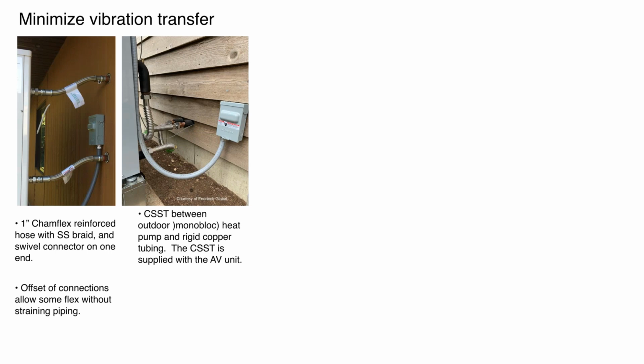This is another approach. This is a corrugated stainless steel tubing. And you can see, again, it's got unions to fasten to the heat pump or to stub outs coming out of the heat pump, and then some flexible path going back through the piping inside. And again, the idea of the flexible path is to attenuate vibration, and also if there is any buffeting from the wind, any slight movement out there, this takes the strain off the piping. So we aren't directly putting mechanical strain on the piping connections on the unit. And of course, you see the disconnects that are required by code out here.